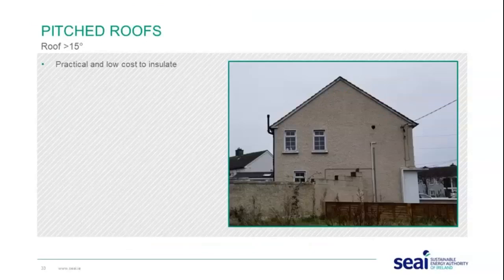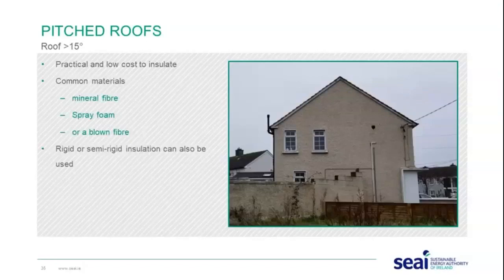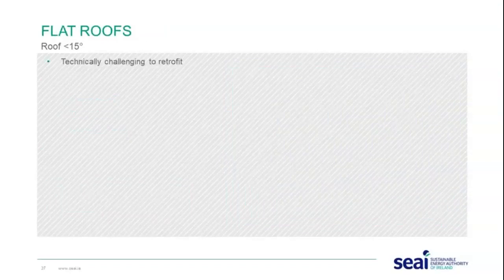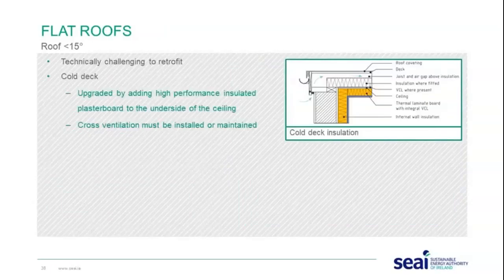Pitched roofs are any roof with a pitch greater than 15 degrees. These are generally low-cost to insulate. Common insulation materials include mineral fibre, spray foam, or blown fibre, and rigid or semi-rigid insulation can also be used. The target scheme U-value for insulation at ceiling level is 0.16. Flat roofs — those with a pitch less than 15 degrees — are sometimes technically challenging to retrofit.